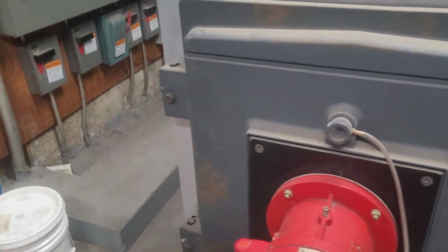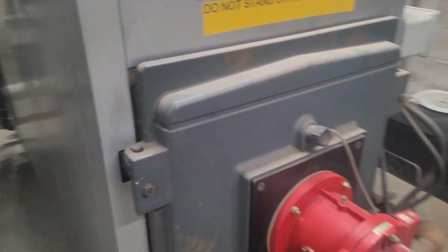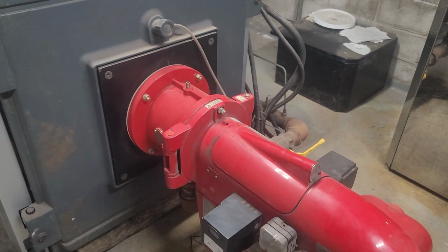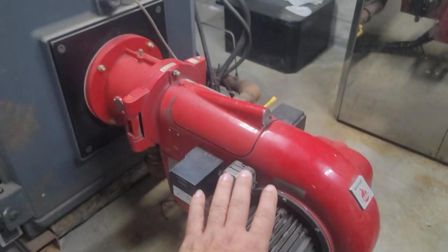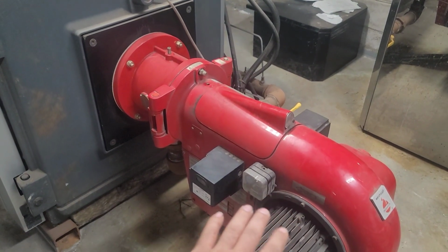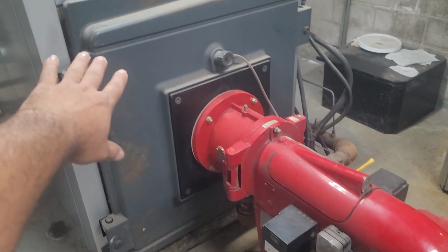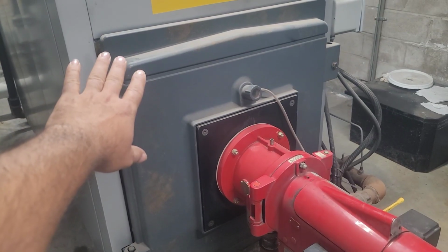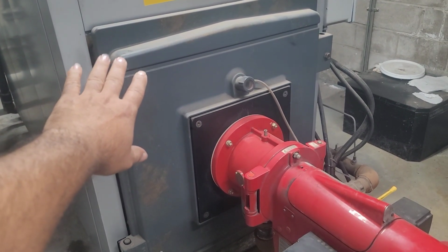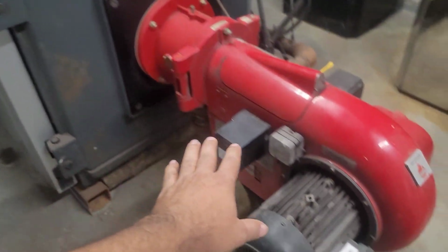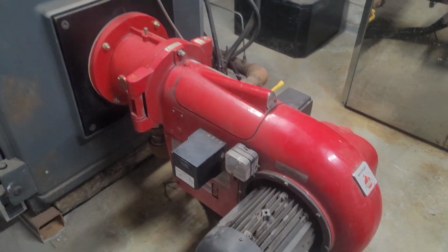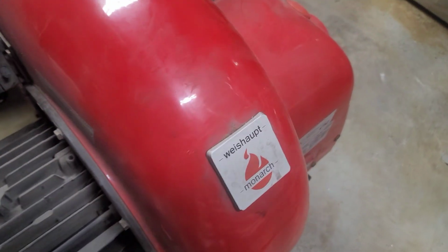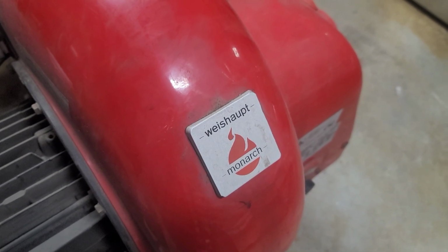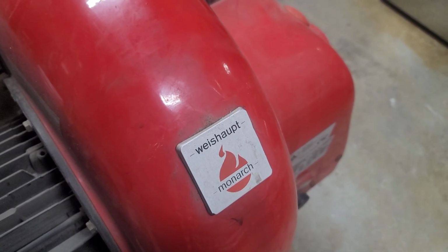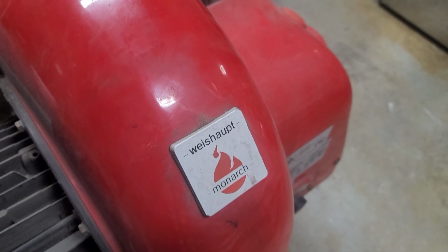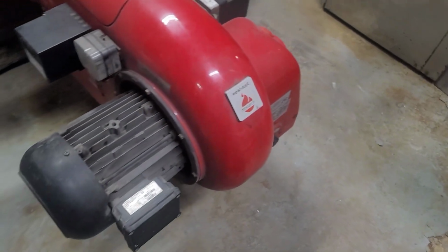For the preventative side, we also recommended to replace a flame rod and an igniter. The unique thing about this boiler, so this part which contains a heat exchanger is from Viessmann, but the burner, the whole red thing, is from this company. I don't know how to pronounce it. Maybe you can.